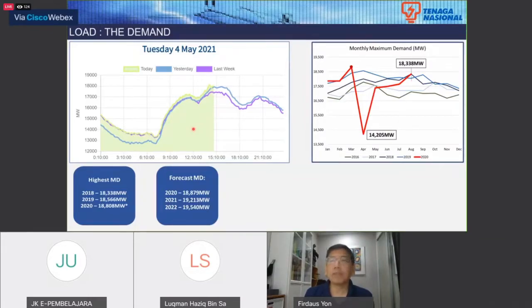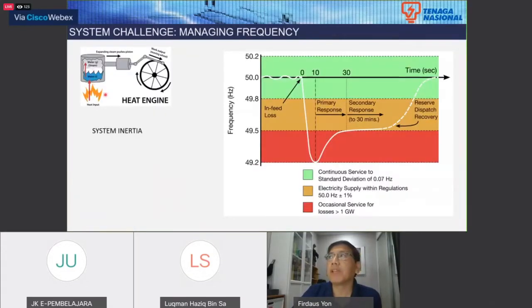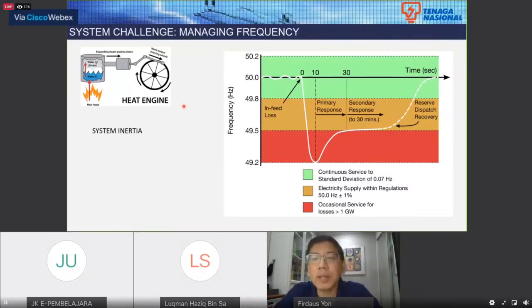The first thing I mentioned just now, we're doing balancing, and then we're looking at frequency as well as voltage. So it's like driving a car, you need to look at your speed, I think that's all you do. So when we drive the power system, we look at the frequency and the voltage. Frequency, we look at it to make sure that the supply matches the demand. And then the voltage, we look at it to make sure there's enough VARs in the system to drive power flow.